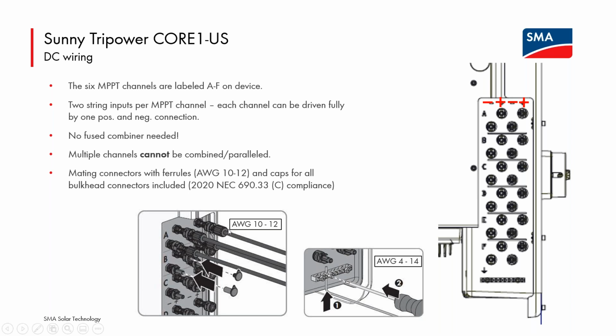The bulkhead connectors that we provide, I want to make sure that folks are aware, the connectors are for 10 or 12 gauge conductors. If you are doing a paralleling of the positive and negatives at the array and bringing back a single positive and negative and upsizing those conductors, you can source from Amphenol connectors for bigger gauge wire, but what we're including in the box with the inverters are for 10 or 12 gauge wire. And below that DC input connection, there's a small equipment ground bus bar for the DC side.